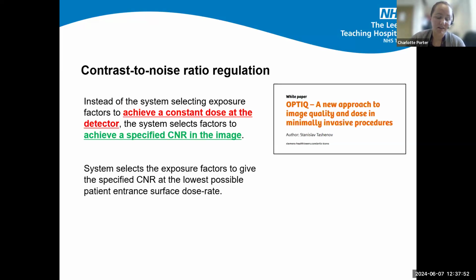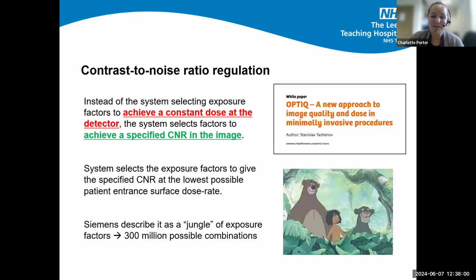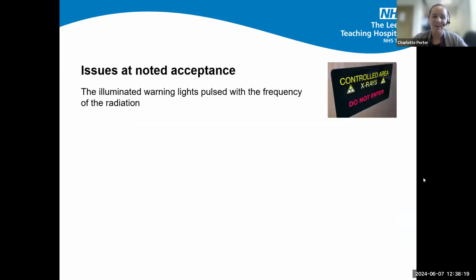So essentially the system is trying to select exposure factors that will give that specified contrast to noise ratio at the lowest possible patient entrance surface dose rate. Siemens described it multiple times as a jungle of exposures to me. Apparently there are about 300 million different possible combinations. So obviously this is quite a complex piece of kit, and sometimes it can pick quite different exposure factors to achieve that specified CNR.